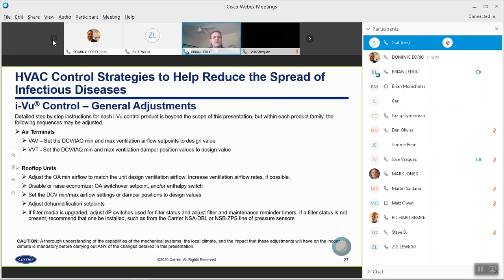Disable or raise the economizer switchover point. Again, this is in situations where you're trying to increase the amount of ventilation. Obviously, you have to go back to the concerns about the capacity of the unit, but they're recommending, if you're going to push the economizer open further, to raise the OA switchover or the enthalpy switchover point. As I mentioned, what to do in terms of DCV, dehumidification. Again, if you're wanting to maintain between 40 and 60, you may have to look at your set points.